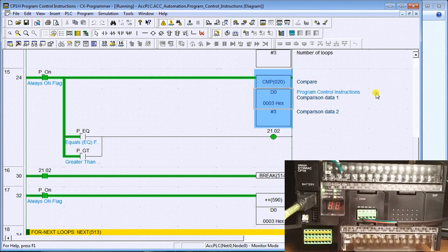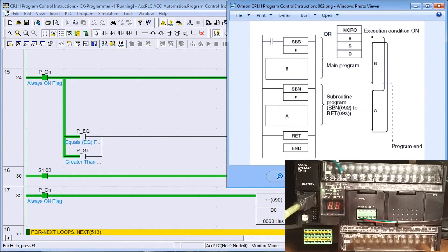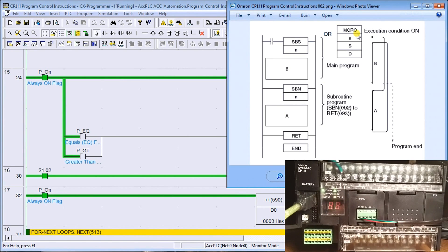The next topic is subroutines. We have subroutine call, macros, subroutine entries, returns, and global subroutines. Basically we have a subroutine name and we either call it directly or call it via a macro. When we call a subroutine, it goes to that subroutine number, executes that code, hits the return, and then returns to the line after which the subroutine was called. With a macro, prior to executing it will set input and output registers to the macro area, so we can use the same code on several different input and output conditions.